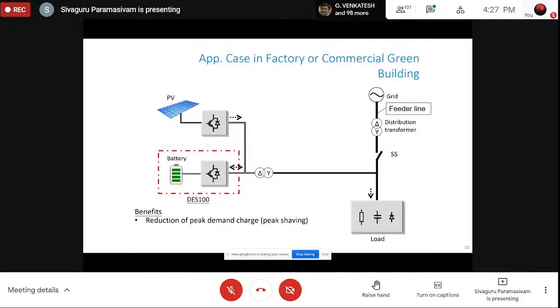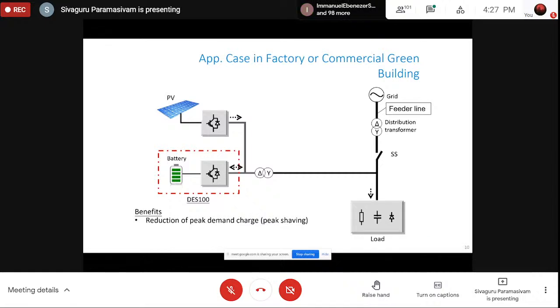But in the battery configuration, you can see that the arrow is marked on both sides, which means the battery DC can be converted with a battery inverter to AC. At the same time, when we have a need to charge the batteries, we can pull the power back from the grid or back from the PV to charge the batteries, which means it is a bidirectional architecture. That's very important to understand the difference. So we use the same switch, same IGBTs, same capacitors and everything, but the way we use the network is like, here it is bidirectional and there it is unidirectional. And the control system plays a major part here in taking care that whenever there is a switching between the direction of power flow, nothing happens to the system. So that's one interesting concept.